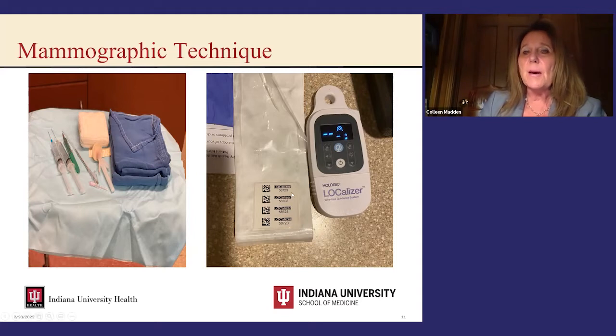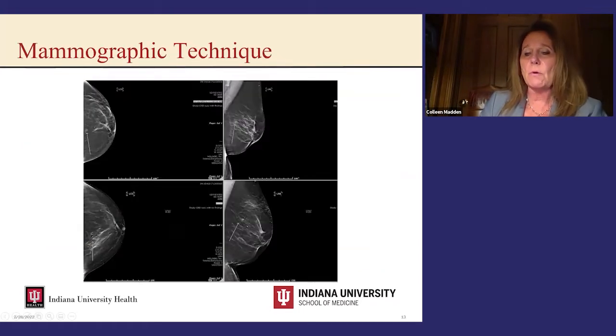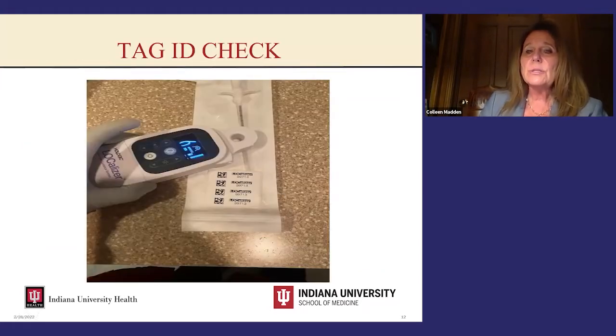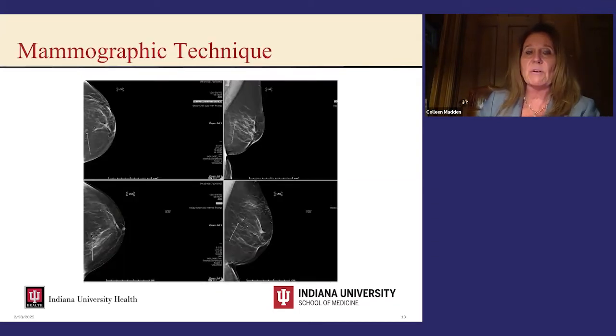This is the localizer or the reader system here. And one of the things that we always do to start is we always check the ID to make sure that the ID in the needle applicator and on the reader system, the same number comes up, and we make sure that it works. I've not had any problems with them not being able to detect it, but just always to be careful.